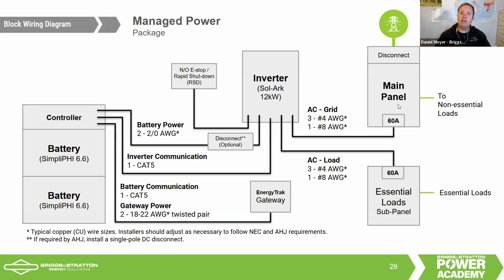What's unique to Sol-Ark and a lot of these other hybrid inverters we partner with is they have what's known as UL 1741 CRD PCS control. That means we can now land a 60 amp breaker here and draw 60 amps out of the main panel, 60 amps out of the inverter, to pass through and feed our backed-up loads panel. But we program the Sol-Ark so that it will never backfeed more than 40 amps.